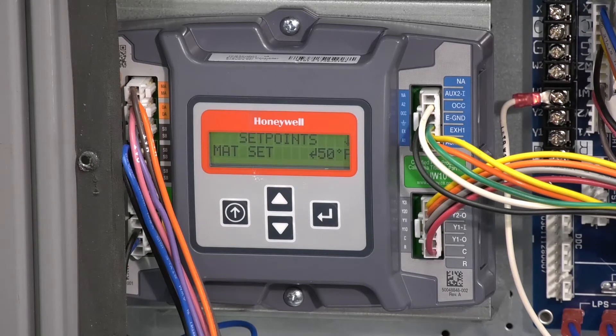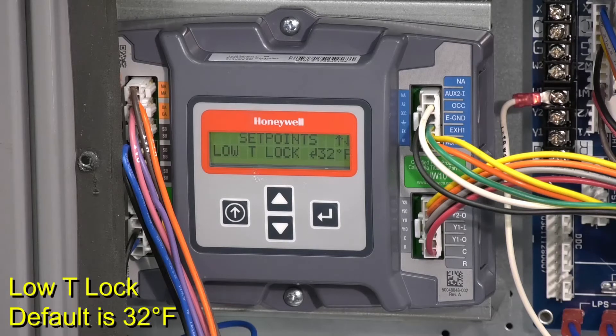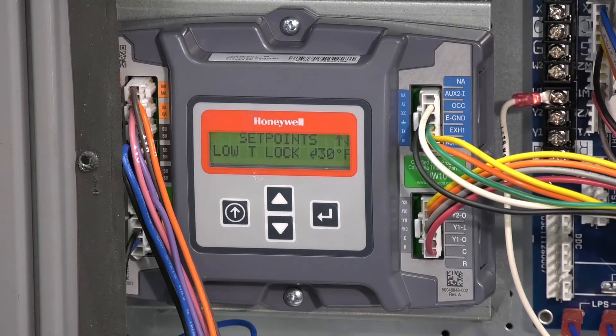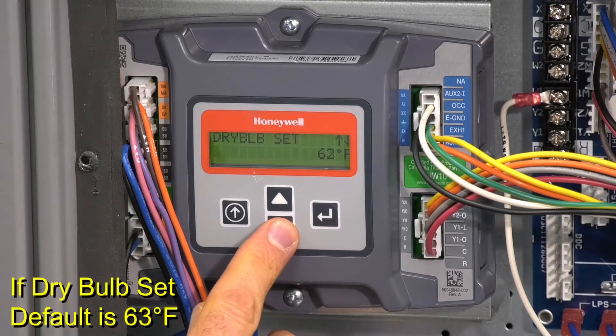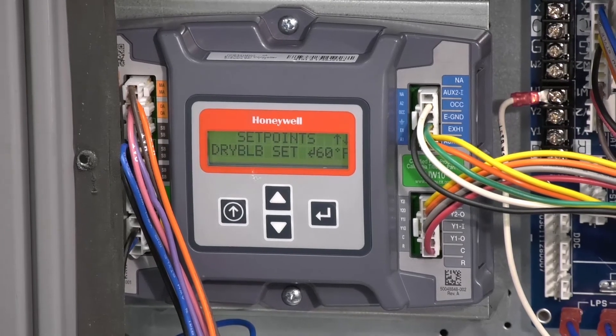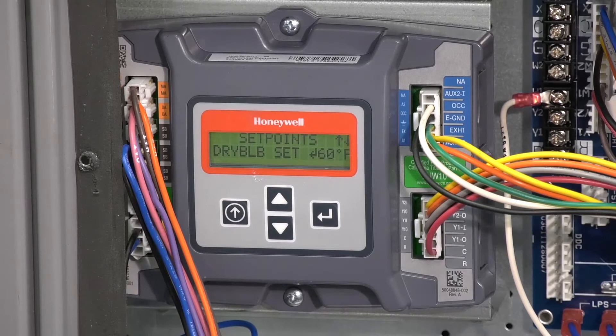Under set points, scroll down to low T-lock. This setting locks out the compressor or mechanical cooling at a given temperature. The default is 32 degrees, but the controller's range is from minus 45 to 80 degrees. We'll scroll down to 30 degrees for this application and push enter. If you have an economizer with a dry bulb outside air sensor, set the dry bulb set. The default setting is 63 degrees, but the controller's range is 48 to 80 degrees. We'll set the dry bulb set point to 60 degrees and push enter. If you have an enthalpy outside air sensor instead of a dry bulb, you'll see and set the enthalpy curve setting, which is used if your economizer has a single outside air enthalpy sensor. There are five enthalpy settings, ES1 through ES5. Check the economizer literature for the limits for each of these settings.